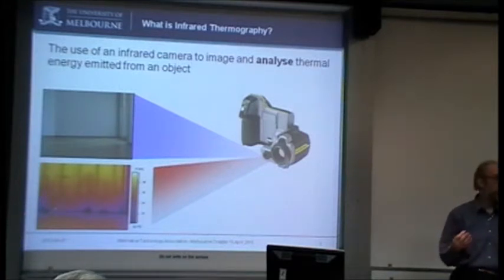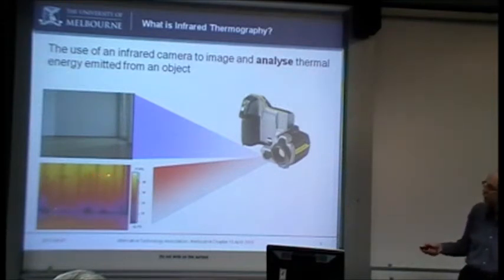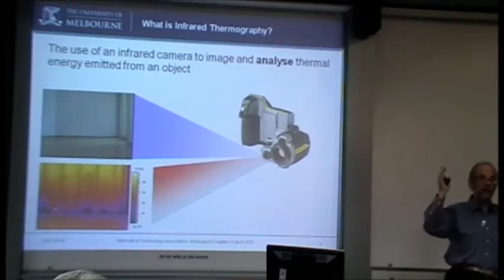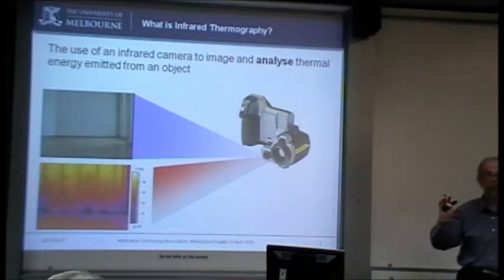So in Australia, where we quite often do the thermography in buildings in summer, you will actually see these looking hot and the in-betweens looking cooler. And so that's again where you've got to get your head around it. You get a reversed image of what you're used to seeing. And it really is one of the traps of going to some of the overseas courses, because they tend to only look at cold weather surveys.